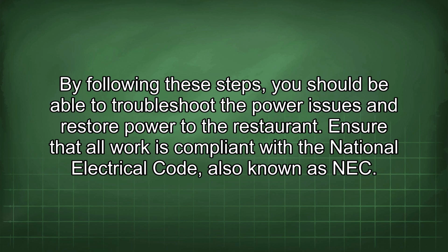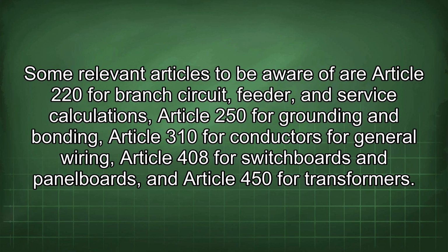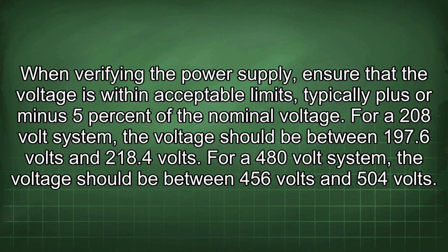Ensure that all work is compliant with the National Electrical Code, also known as NEC. Some relevant articles to be aware of are Article 220 for branch circuit, feeder, and service calculations, Article 250 for grounding and bonding, Article 310 for conductors for general wiring, Article 408 for switchboards and panelboards, and Article 450 for transformers. When verifying the power supply, ensure that the voltage is within acceptable limits, typically plus or minus 5% of the nominal voltage. For a 208-volt system, the voltage should be between 197.6 volts and 218.4 volts. For a 480-volt system, the voltage should be between 456 volts and 504 volts.